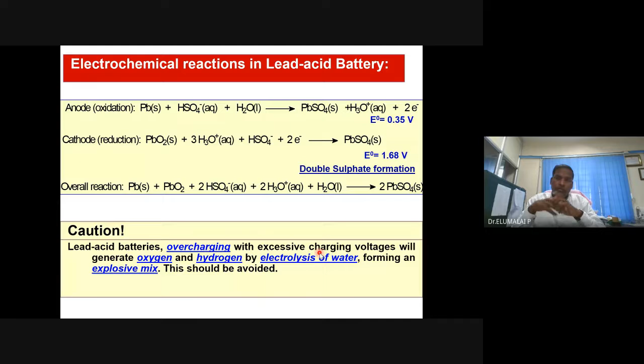And if too much volume of hydrogen and oxygen are generated by the decomposition of the electrolyte water, what will happen? It might lead to explosion or evolution of the oxygen and hydrogen gases from the batteries. This is possible in the case of maintenance-requiring batteries, or flooded lead acid battery.